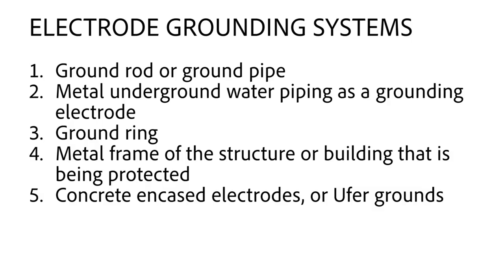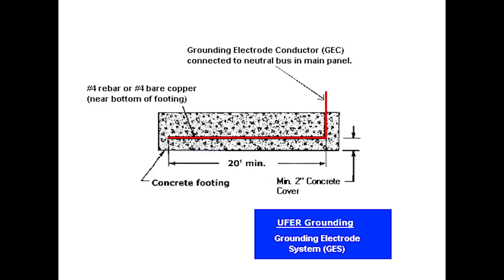In regards to the next method, which we also mentioned in our last video, the use of concrete encased electrodes or Ufer grounds are also acceptable. In order for this type of electrode to meet NEC standard it must be encased in at least two inches of concrete and that concrete should have direct soil contact. Also, the electrode should be located near the bottom of the concrete foundation and the conductor should be no less than 20 feet long and no smaller than four gauge wire.